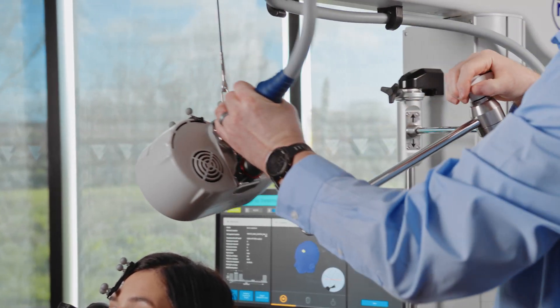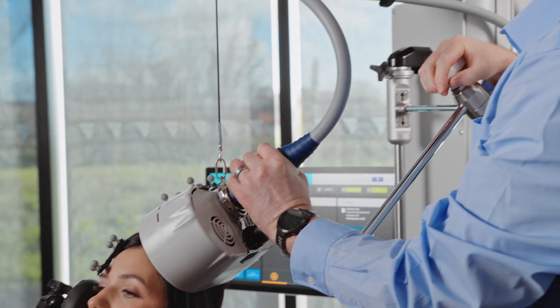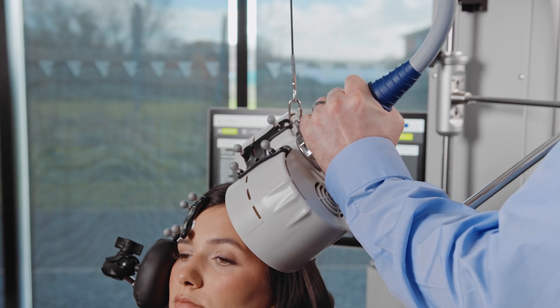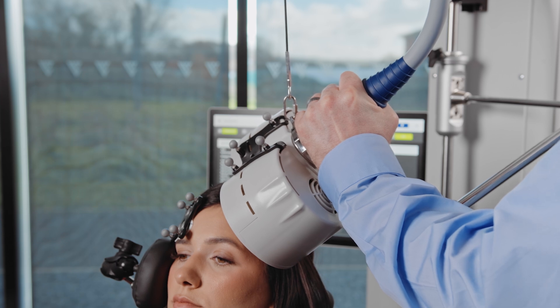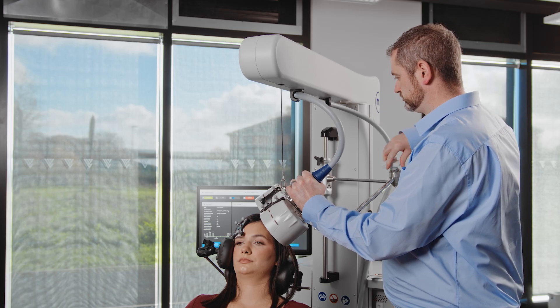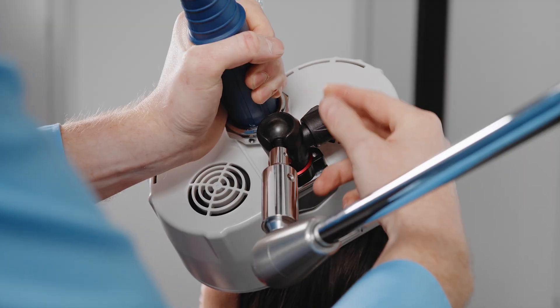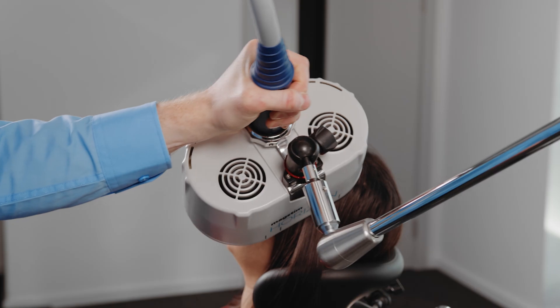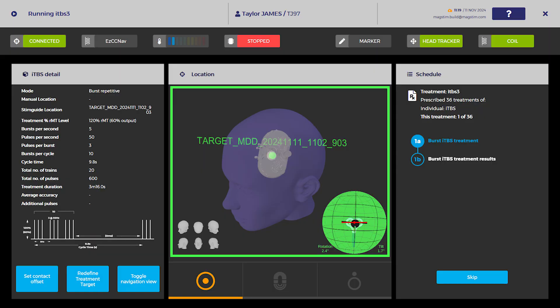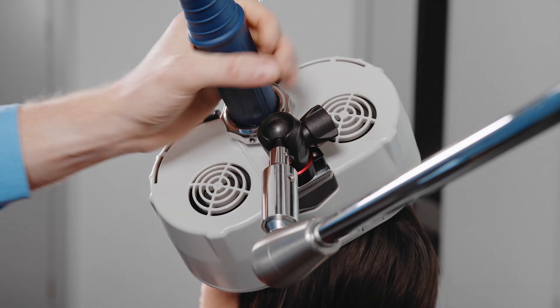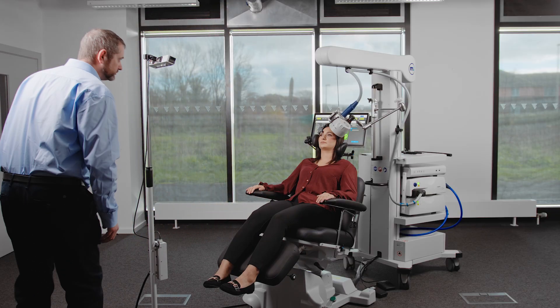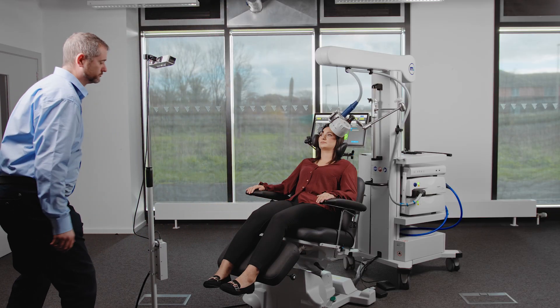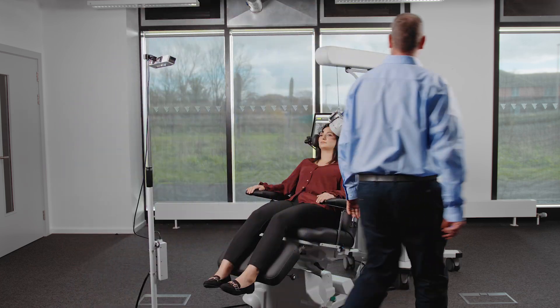Unlock the central locking knob fully to adjust the coil position. Position the coil on the treatment location roughly at a 45-degree angle and tighten the central locking knob. Unlock the coil angle lock and refine the coil angle so that all measurements show green. Tighten the coil angle lock to secure the coil position. Visually confirm the coil is at a 45-degree angle to the midline, tangential to the curvature of the head.